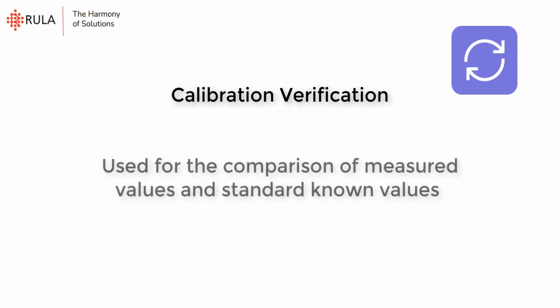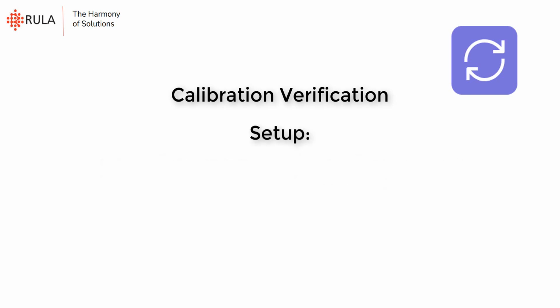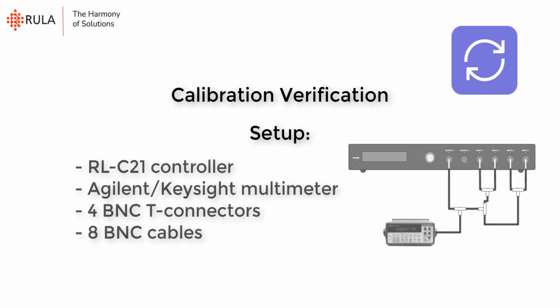This option is used for the comparison of measurement values delivered by a device under test with standard known values. To use this feature, you need to have a RL-C21 controller, Agilent or Keysight multimeter or the equivalent, 4 BNC T connectors and 8 BNC cables.